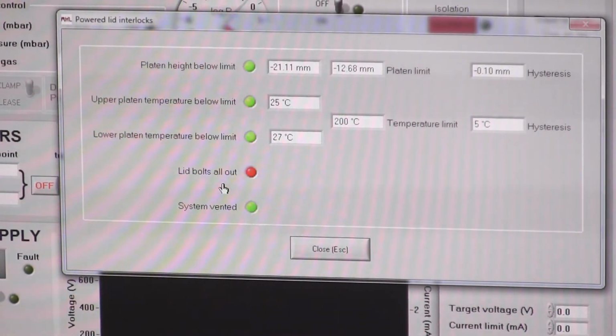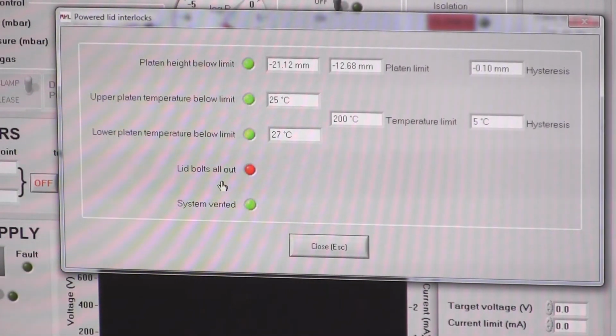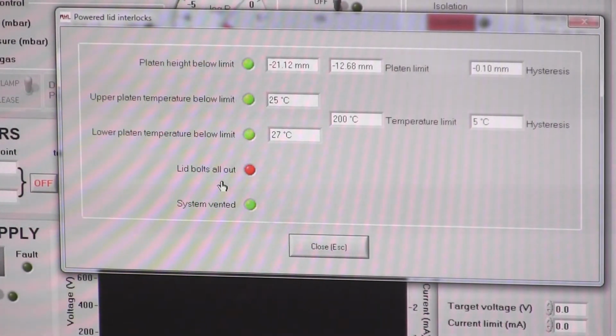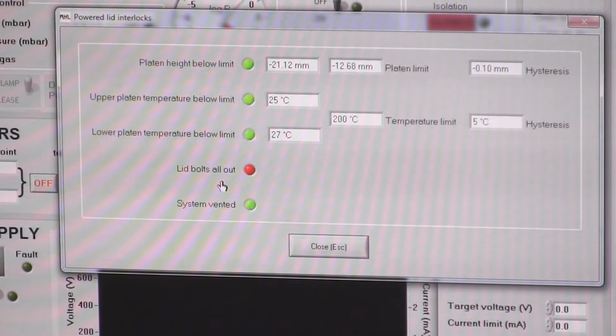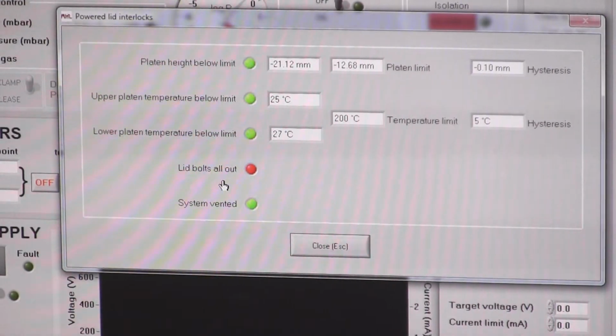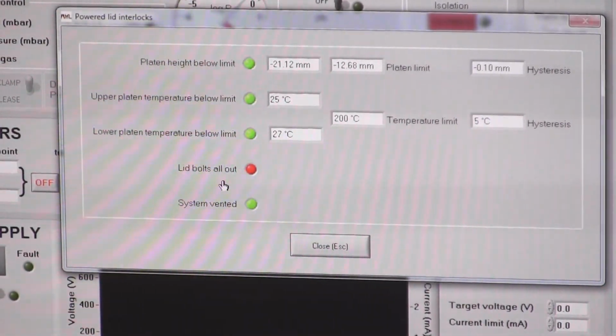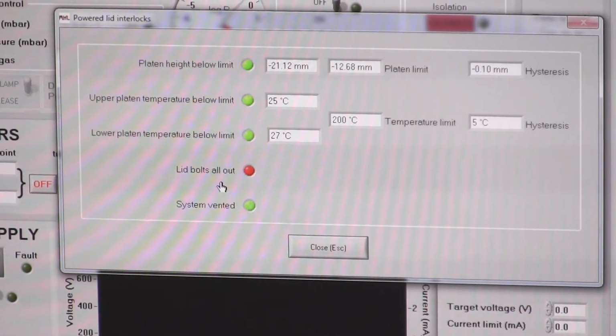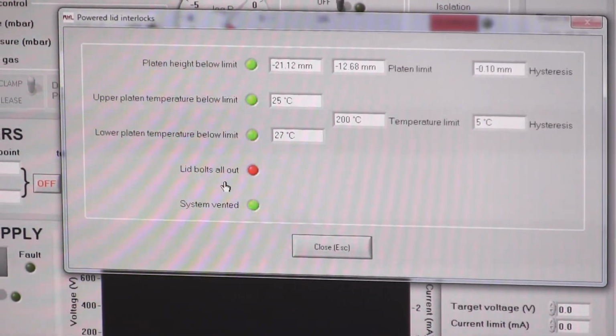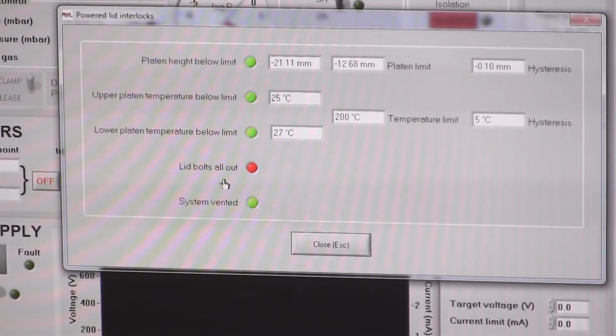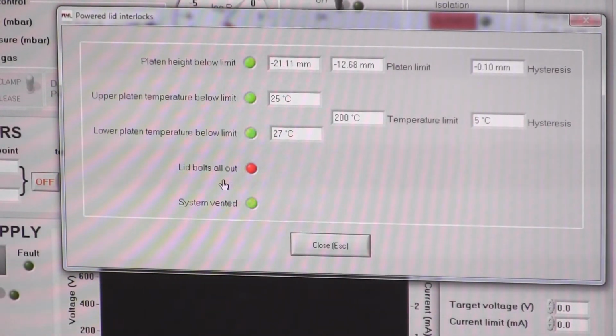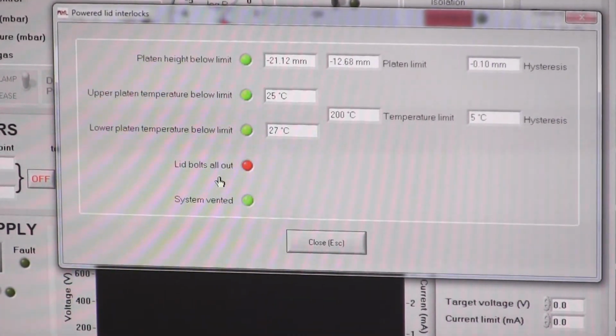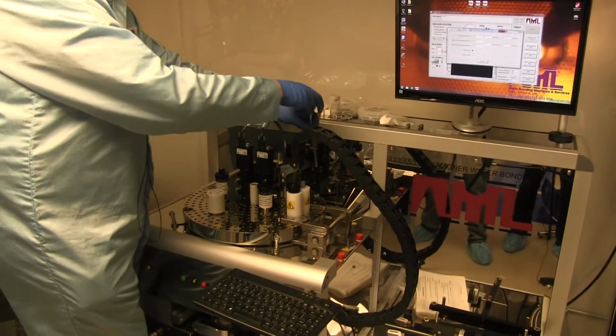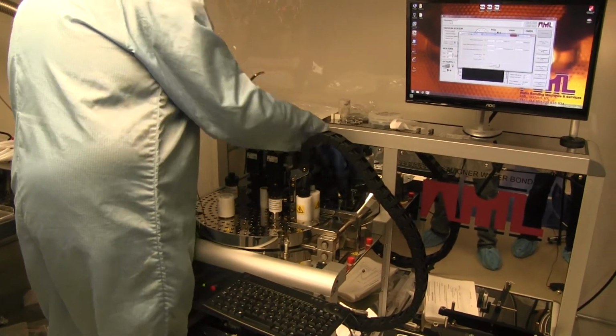It won't allow us to try and open the lid while the bolts are in, because doing so would just grind the motor. Similarly, the bolts need to touch some sensor. Yeah, there are micro switches on the bottom. There are two micro switches, one normally open that tells the software that the bolts are in, one normally closed that tells the software when the bolts are out. So it knows when they're either all in or all out. If I only take one out, it knows that some are still in. When I've got them all out, that will turn green. There we go. Now all the conditions have been met.